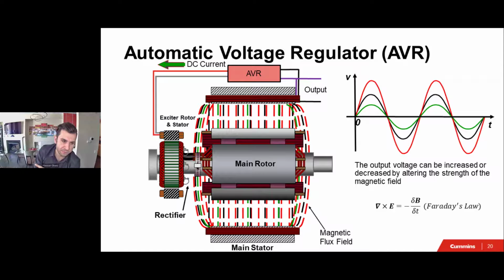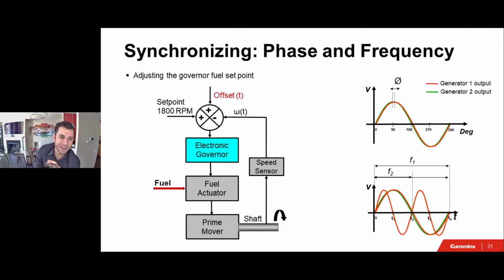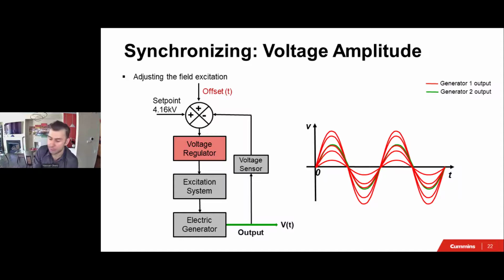Okay, so if we could tie it back to synchronization, right? To synchronize phase and frequency, I'll just give you the answer, we control the fuel. If I have a set point, for example 1800 RPM, we're sensing that, and the engine governor sets that fuel for me, sets that engine speed and maintains it at 1800 RPM. Now, if I need to change the output voltage from the generator, to get a little bit higher voltage or reduce the voltage to match the other source that's online, again, I have a set point, and then I change the DC field that goes into that rotor that cuts through the stator where that output voltage is generated, or induced, I should say, the most technical term.